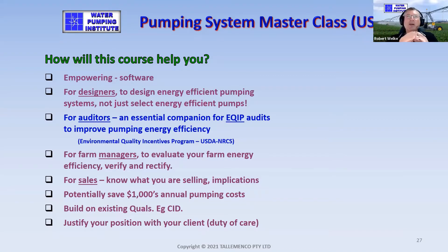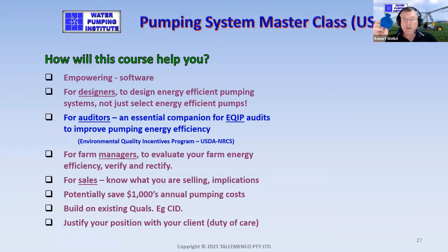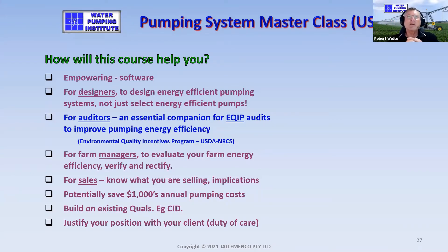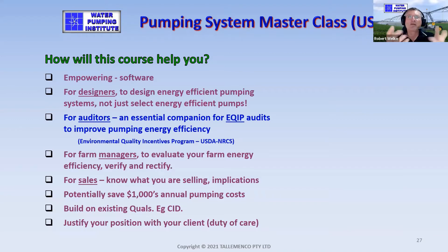There's no real value in just selecting the most efficient pump, because these days they're all about 80% efficient. The real objective is to get the pipeline system into an optimized energy efficiency. For auditors, this course and its software would be an essential companion for EQIP audits — that's the Environmental Quality Incentives Program, run through the NRCS.